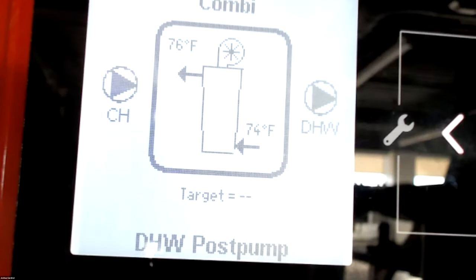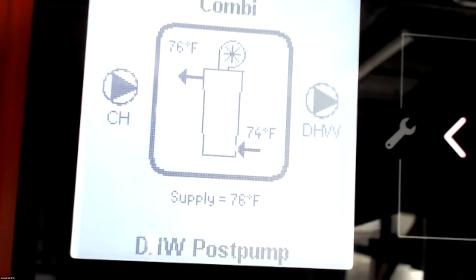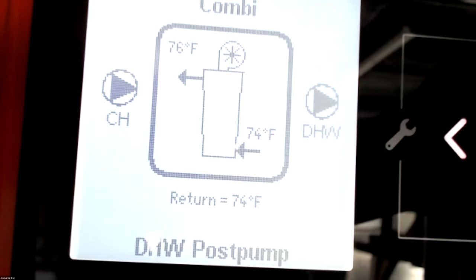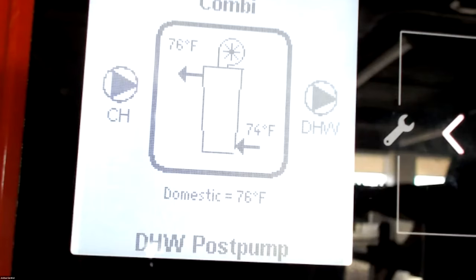The target temp. So if you're calling for heating, our target would be listed there. If we are running a thermostat and set point only, and you had it at 180, it would just show 180. But if we were using the outdoor sensor and we were doing outdoor reset, whatever our curve was, that would be your target there. And then it shows again the supply system and return sensors, and then your domestic sensor, and the domestic output. That's some quick information right there that you can look at.